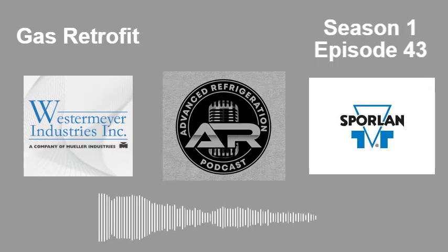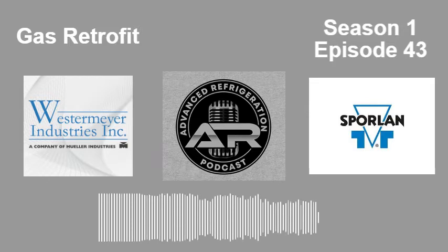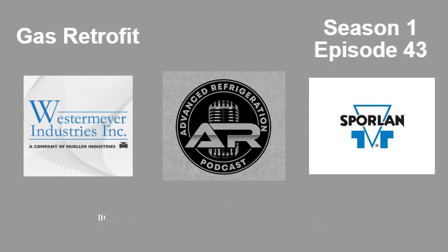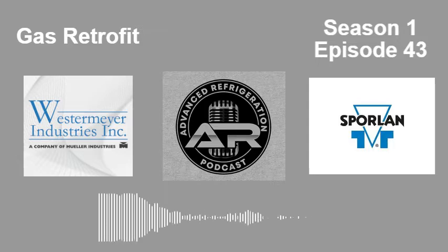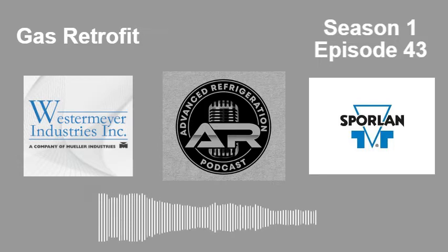I try not to do retrofit caps on high side ball valves. Your main ones, like your condenser ball valves, you don't want to high side cap those. You want to replace them because if they leak internally, you're up the creek. You might as well get them done. As of lately, every spec I've seen come out, we've been changing all high side ball valves. So most major customers want the high side ball valves changed.